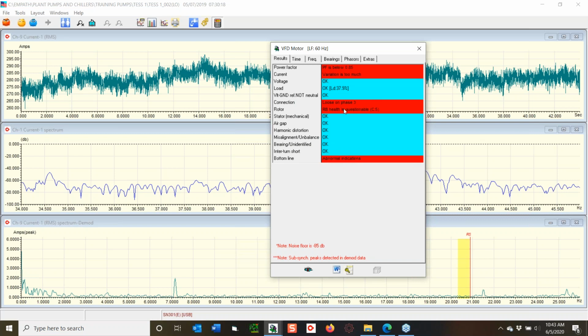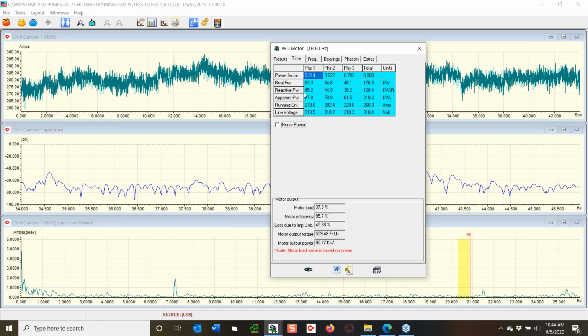So anyways, rotor bar health is questionable, C5. So that means that I want to take a look at that. That does not automatically mean I have a bad rotor bar. I don't see anything for bearings. I don't see interturn short issues and so on. So right now it's not seeing anything in particular. I will then, when I start analyzing, at about 10 dB above the noise floor or 65 dB down, is when I'll also see it with other technologies. So those are usually the alarm rates that I use.